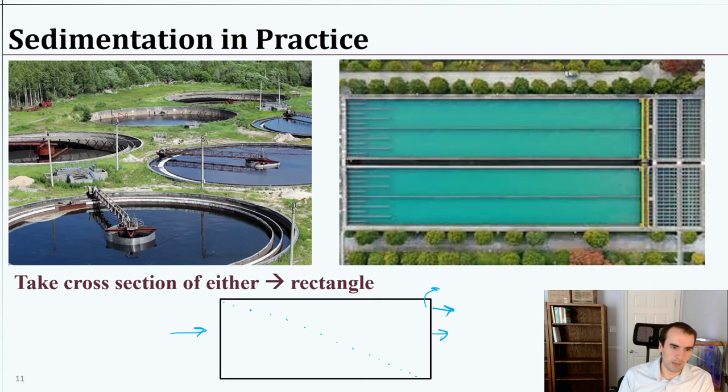A lot of times we collect off the top, but still, we want it to settle before we get to that point. So that's our design criteria, assuming the water is being collected in this manner. So the VS, you're exactly right. VS is the vertical settling velocity. Technically, given the flow term, the advection taking it in the X direction, yes, that is causing the net velocity to be diagonal, but really what we're concerned about is this vertical component. So in that Y direction, you're exactly correct.